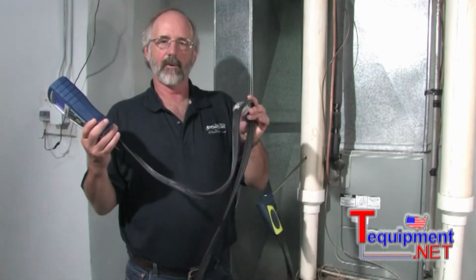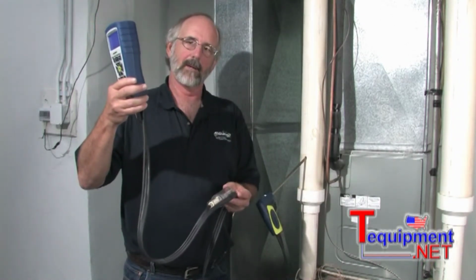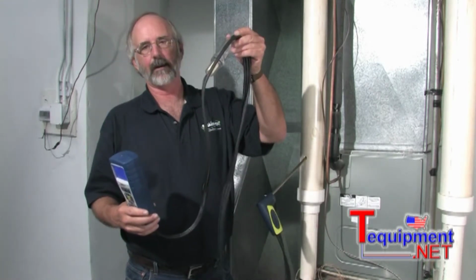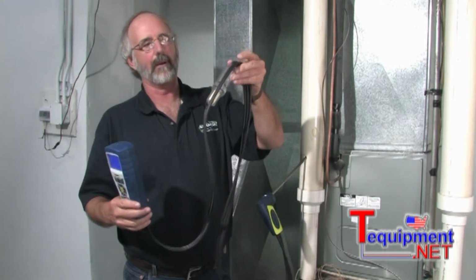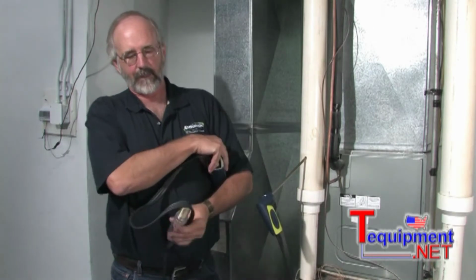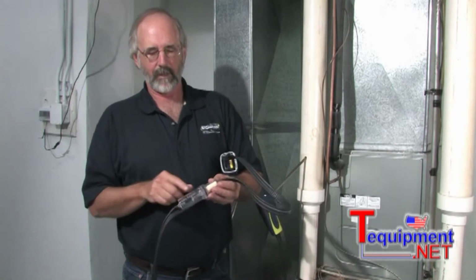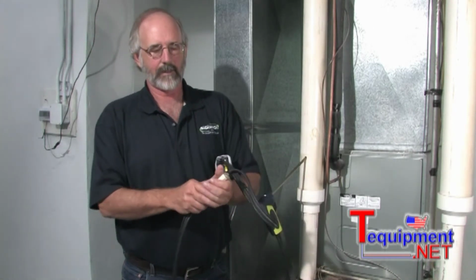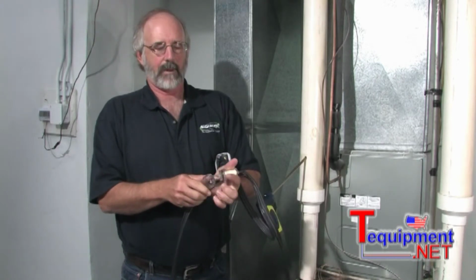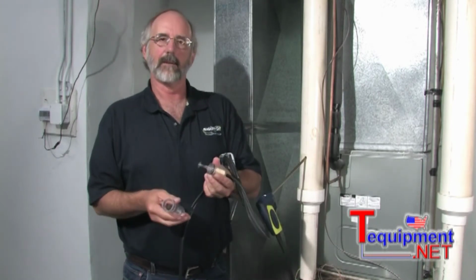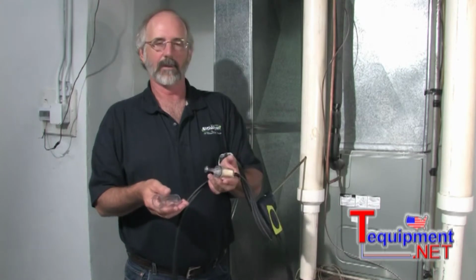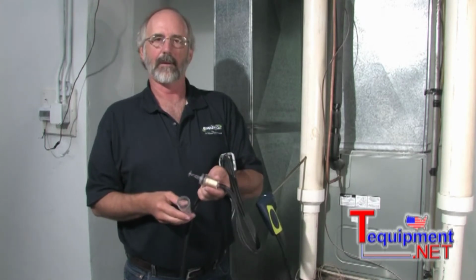You also want to make sure that the moisture trap is always below the level of the instruments. If you get it up here, you're going to end up maybe potentially sucking some water into it. The other thing it's a good idea to do is at the end of each job, if you see any moisture that's accumulated inside that moisture trap, just open it up, empty it out. If it's at the end of the day, just leave it open in the case, let the filter dry out. Let it dry out thoroughly.